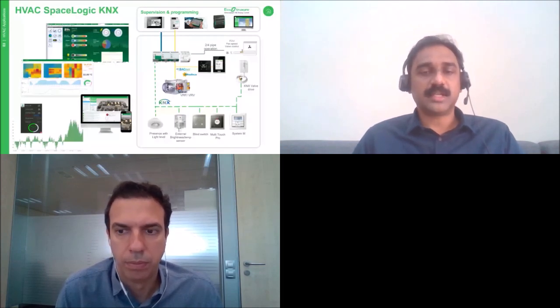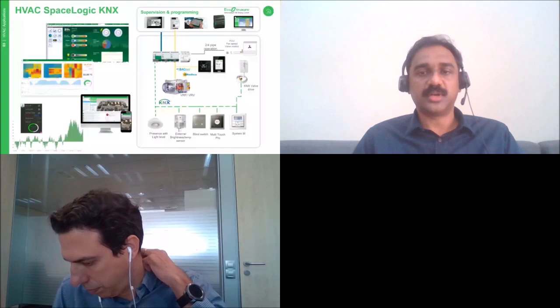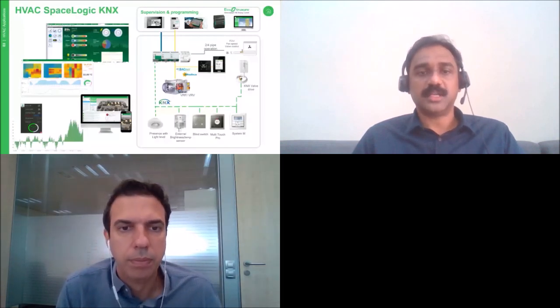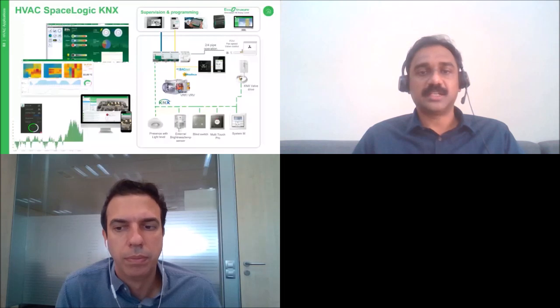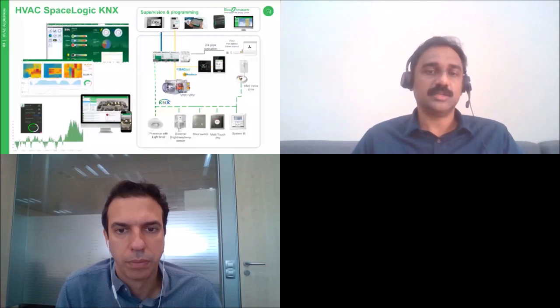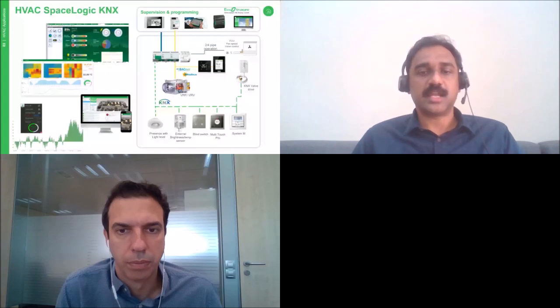The system parameters can be altered to attain the perfect energy-saving scenarios required for the building, at the same time keeping an extreme comfort level. A fully automated HVAC control system allows the user to completely automate the building by different inputs from presence detectors, CO2 or humidity sensors, time schedules, logic functions, etc. to switch between comfort, standby, night, heat or frost protection, or any other predefined modes.